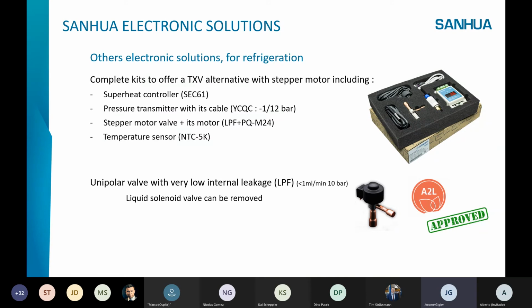The big advantage is for the LPF. The LPF has a very low internal leakage, less than 1 milliliter per minute with 10 bar pressure difference. So we can remove the liquid solenoid valve on the liquid line of the circuit. That is the big advantage of this valve. All this kit is also approved for HFO refrigerants, for example 454A, 454C.